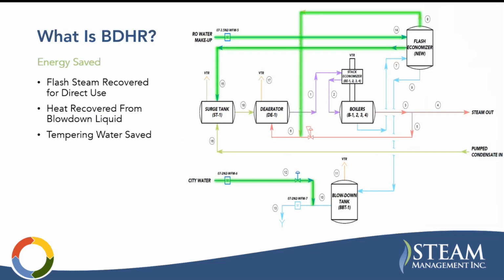So what is saved here? First you have your flash steam, right? We just talked about that. That's clean steam that's being captured. You're sending that straight into your deaerator, downstream of your PRV, and then your PRV is making up the remaining demand of the deaerator for steam. This is like a balanced line. So your flash economizer, your flash tank, is going to basically operate in balance with your deaerator pressure. And that pressure is going to drive how much flash steam is available from your blowdown. So your boiler operating pressure, you're reducing down to that flash tank operating pressure. That determines how much flash steam comes out.